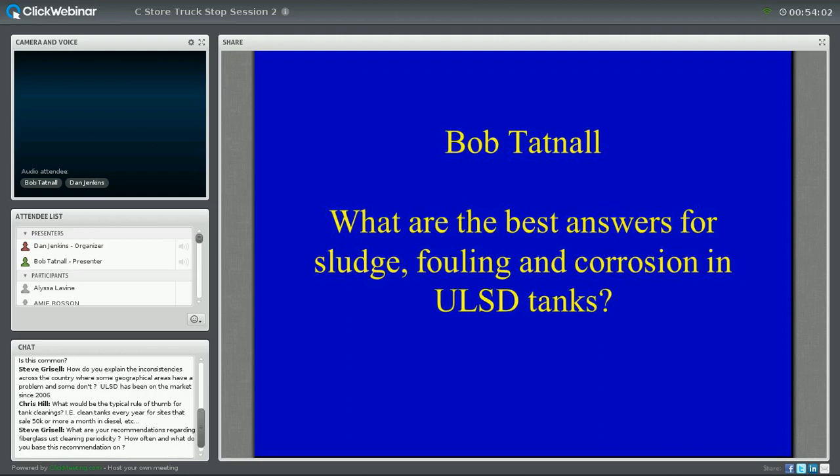even knowing that being a conical bottom tank, the slope is going to go up, and the lowest point in the bottom is right around the perimeter of the tank. That's where we drew our sample. Our bacon bomb came up full of water. So there's a good chance he was delivering big chunks of water with the fuel.